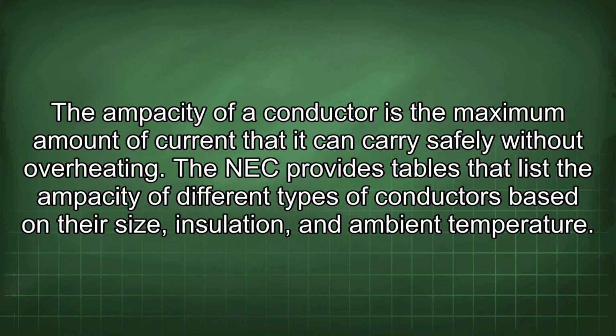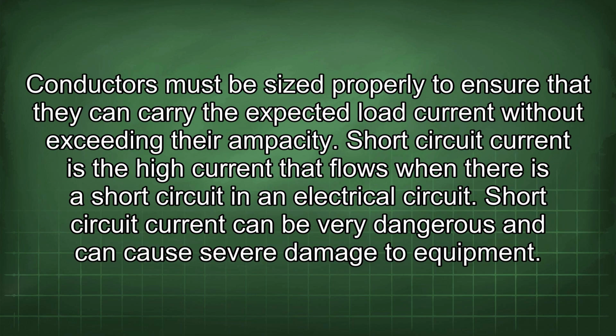The ampacity of a conductor is the maximum amount of current that it can carry safely without overheating. The NEC provides tables that list the ampacity of different types of conductors based on their size, insulation, and ambient temperature. Conductors must be sized properly to ensure that they can carry the expected load current without exceeding their ampacity.